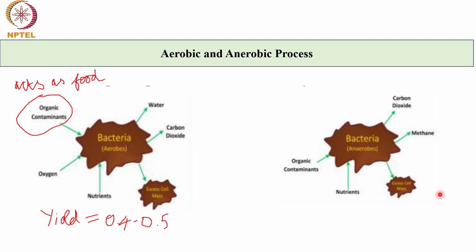See, at the end it is how much sludge is produced, that is, how much volume of bacteria is produced, right? So MLSS can be used for measuring. It is ultimately the suspended solids, whether it is anaerobic bacteria or aerobic bacteria. The concept is you are giving some dissolved organic pollutant, and it is getting converted to bacteria, that is the suspended form of organics. So you can use the MLSS and MLVSS concept for anaerobic bacteria also to evaluate. That won't be an issue.